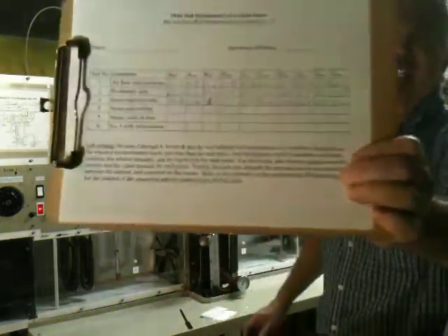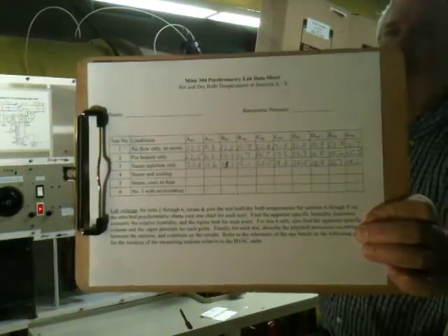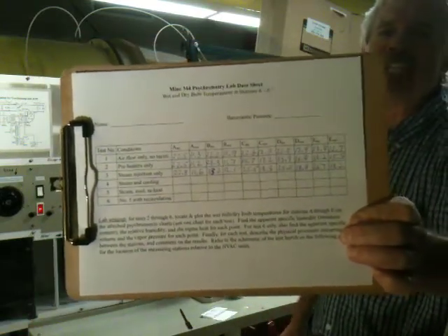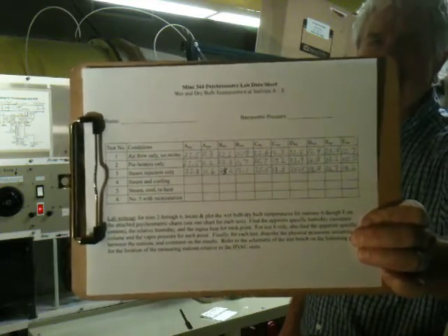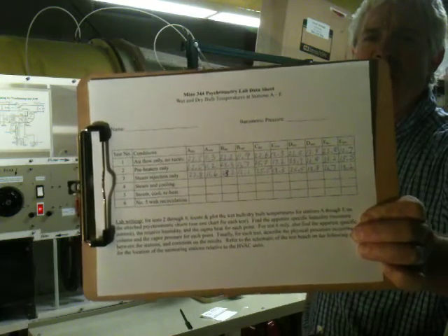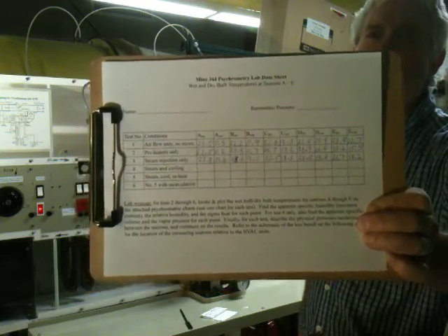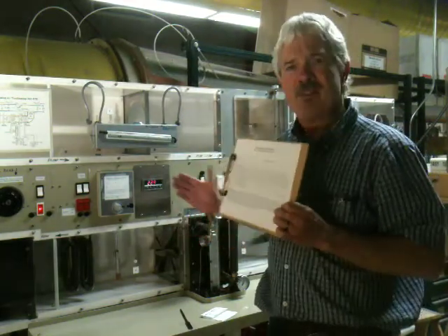You can see that. So the thing of interest, you'll notice that stations C, D, and E, the dry bulb went down compared to the second test because we weren't heating with the direct electrical resistance. But look how the wet bulb temperatures all went way up. And that is a reflection of the increased humidity in the environment downstream from the boiler.